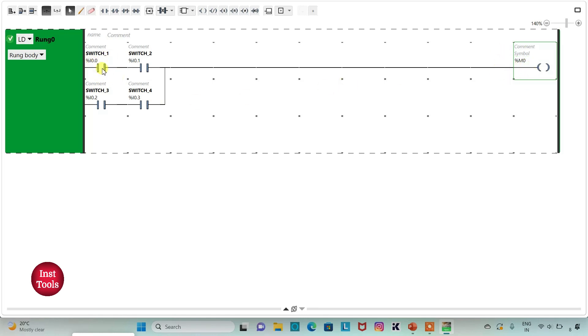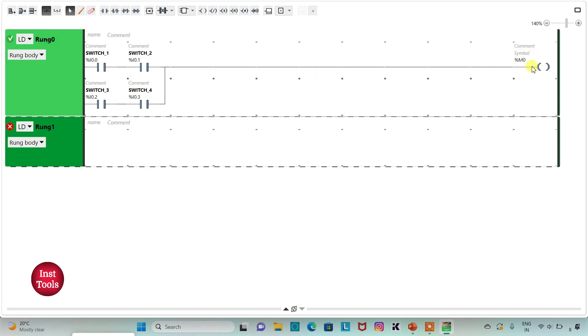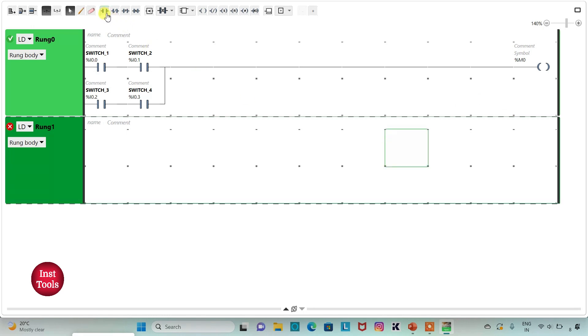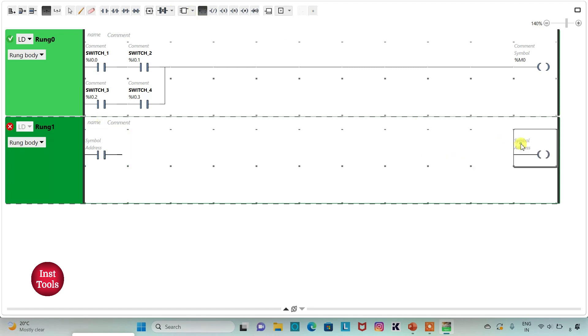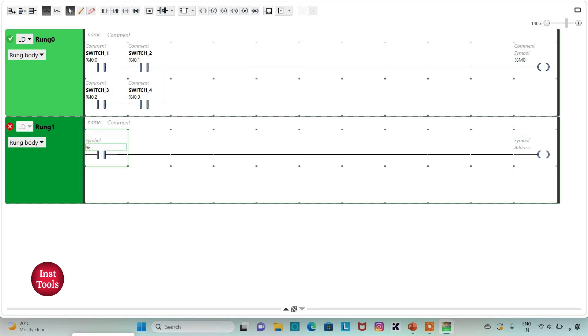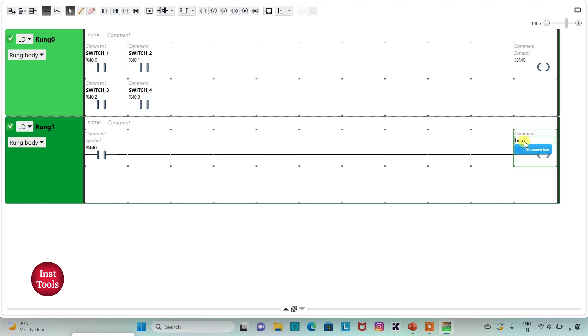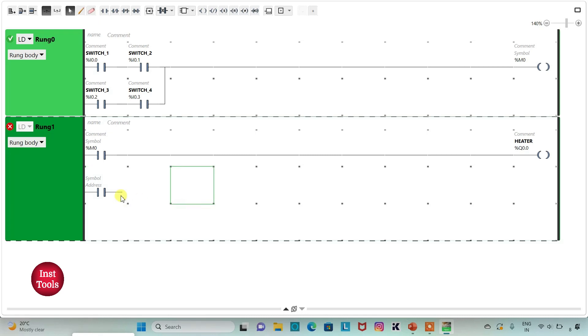So when switch 1 and switch 2, or switch 3 and switch 4 are on, then M0 will be true. We will use this memory bit M0 to turn on the heater. I will insert a normally open contact and a coil — assigning M0 to the contact and Q0.0 (symbol: 'heater') to the coil. We need to latch it, so I will insert one more normally open contact and assign address Q0.0 to it.